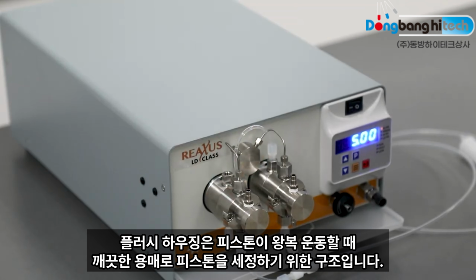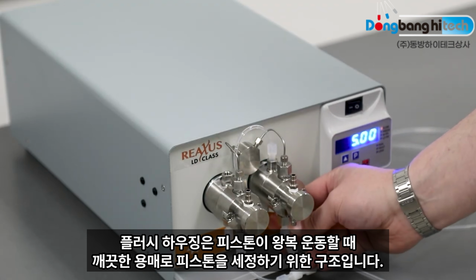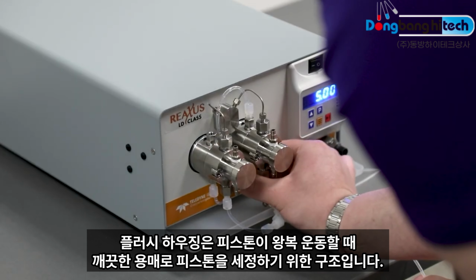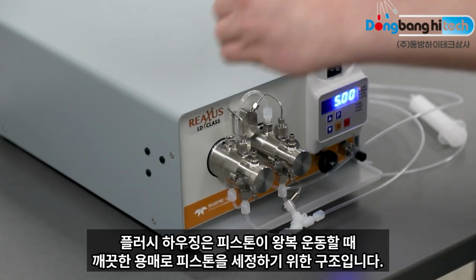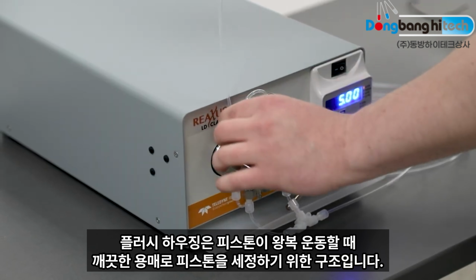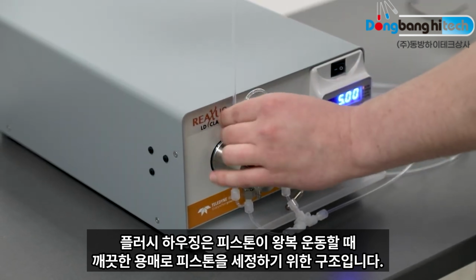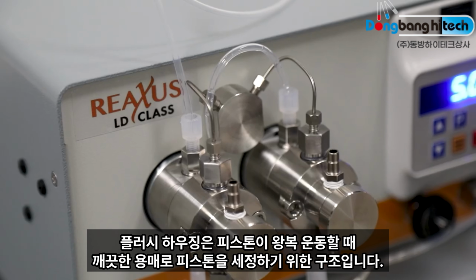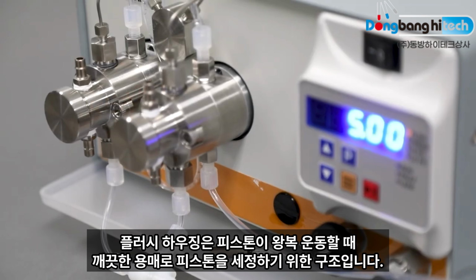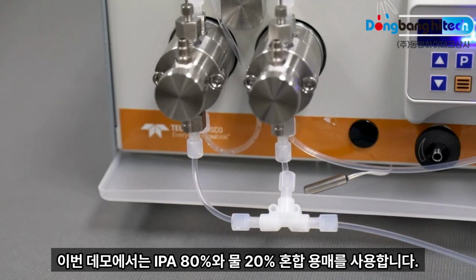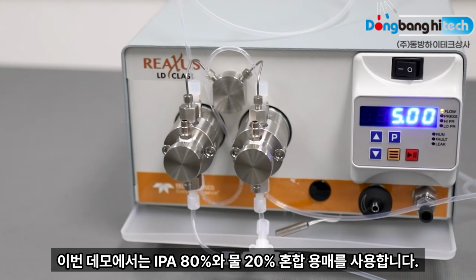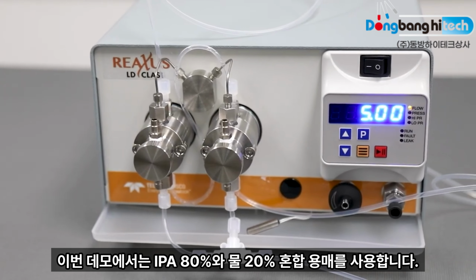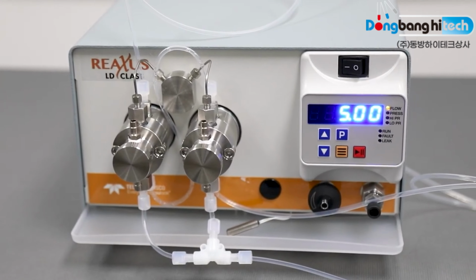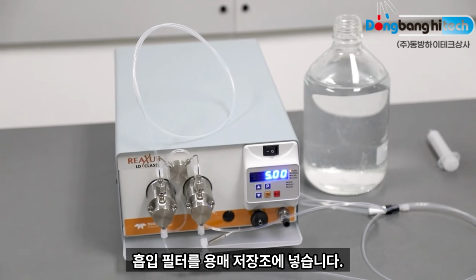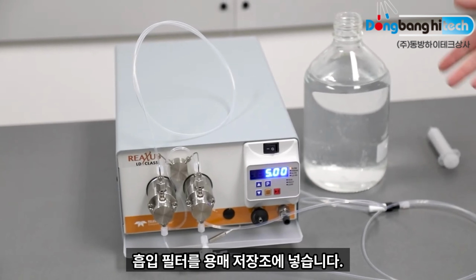We will connect one of these tubing lines to the inlet on the left, and we will have our outlet tubing on the left pump head. Flush housing is intended to flush the piston as it's reciprocating with clean solvent. In this demonstration, we will be using the same solvent that we will be pumping through the system, which is 80-20 IPA and water.